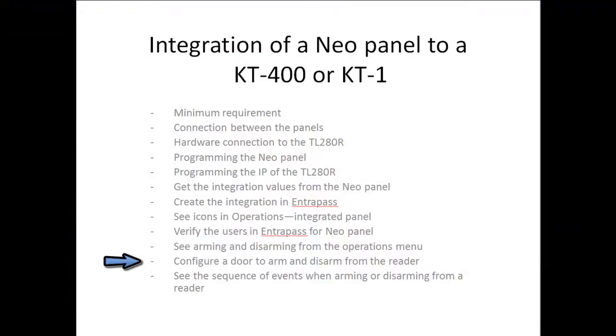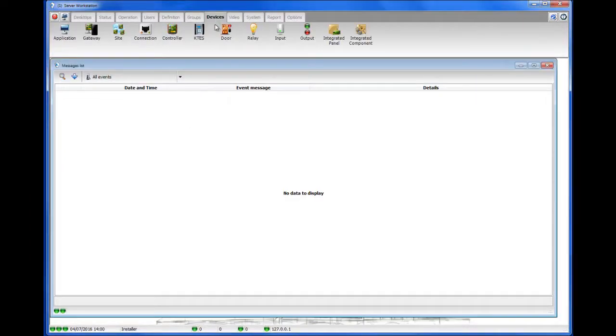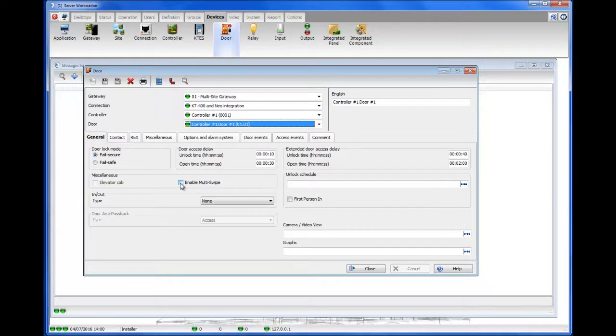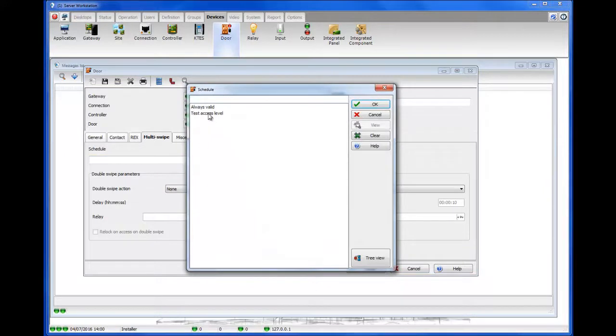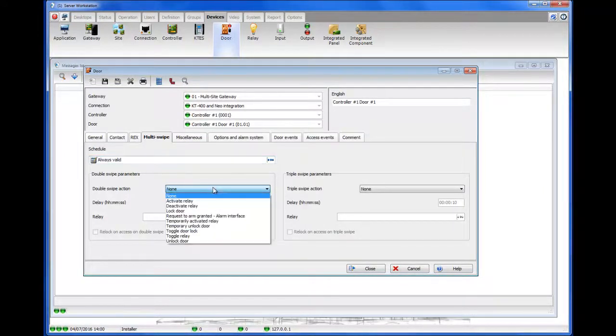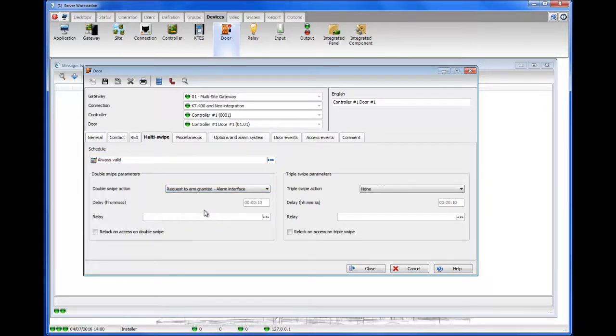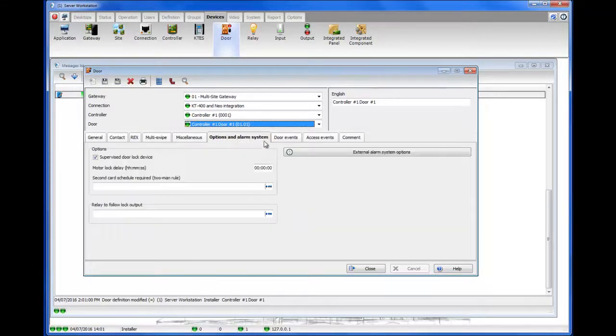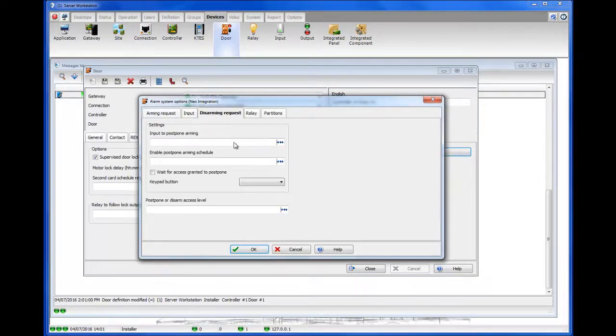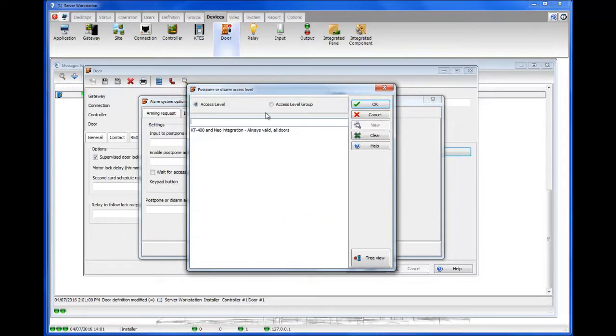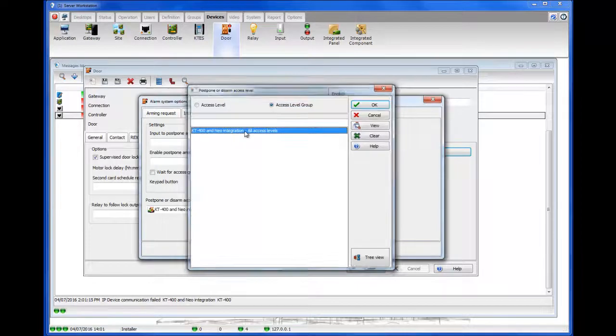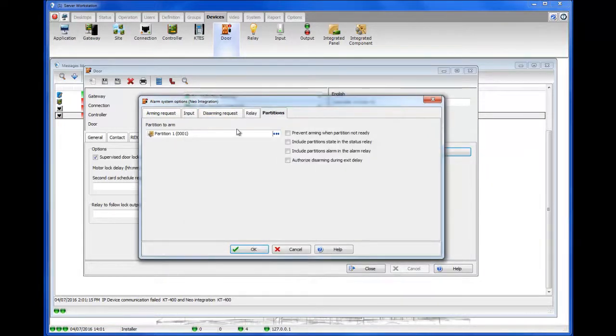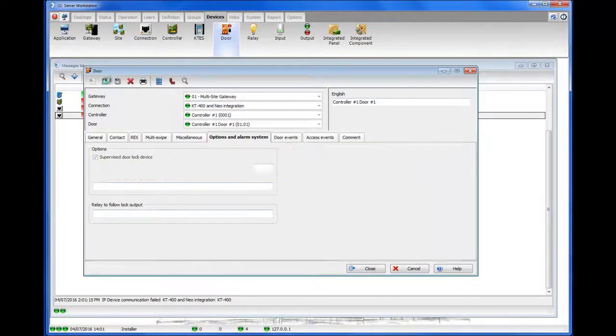Our next step is to configure a door to arm and disarm from the reader. Go to Devices, Door, and select the door you want — let's select door one. Check the checkbox Enable Multi-Swipe, which gives us the Multi-Swipe tab. Set Multi-Swipe Schedule to Always Valid. For the double-swipe action, select Request to Arm Granted Alarm Interface. You can check the checkbox to re-lock on access, which re-locks the door when you double-swipe. Then go to Options and Alarm System tab, External Alarm System Options button, the Disarming Request tab, and select an access level to disarm. Selecting All Access Levels means anyone with door access can disarm. Finally, go to the Partitions tab and select the partition to arm or disarm — in this case, Partition Number 1.